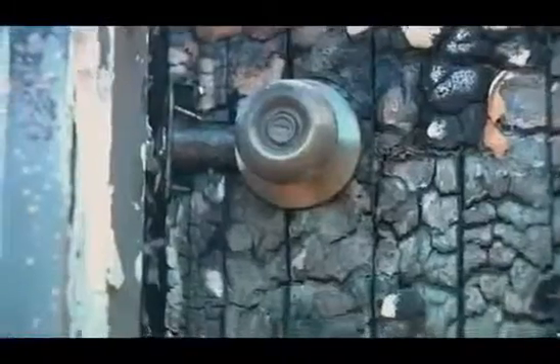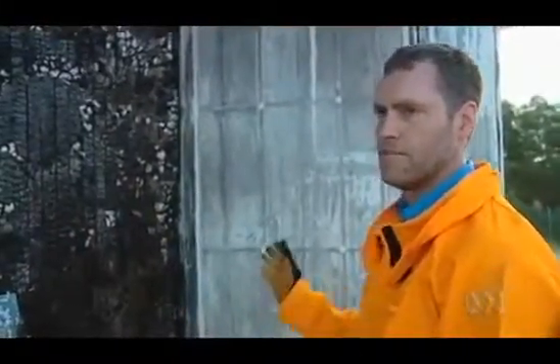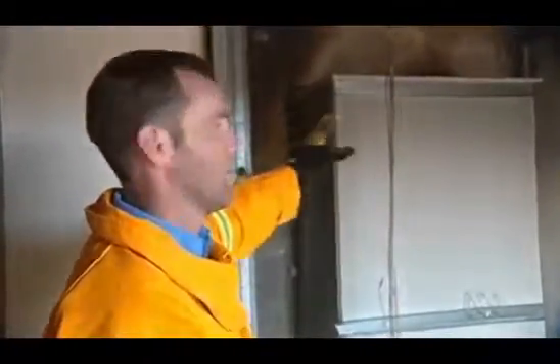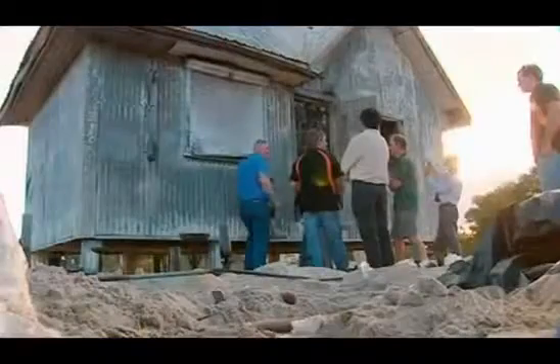So this door would be a weak link? Definitely a weak link in the process. Simply a combination of a timber solid core door and a steel frame isn't an adequate combination in flame zone. So we can see quite a considerable thermal layering effect, and it seems to be smoke and combustion products that have come from the door and the far window.